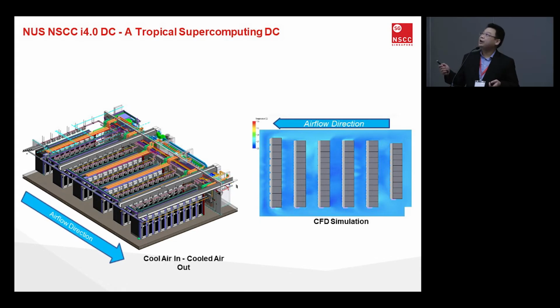Hence the reason why we designed it this way. The rear door behind actually has variable speed fans that suck the air from inside the rack out, and while doing that, it's also throwing the cold air into the next rack. So it gets thrown into this rack, and the cycle continues. Hence the design is done this way, in one direction.